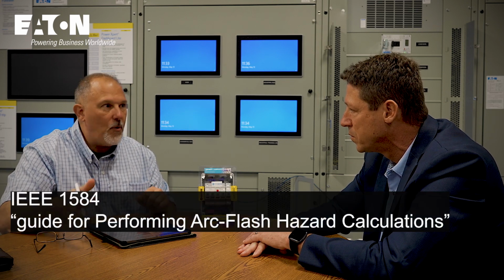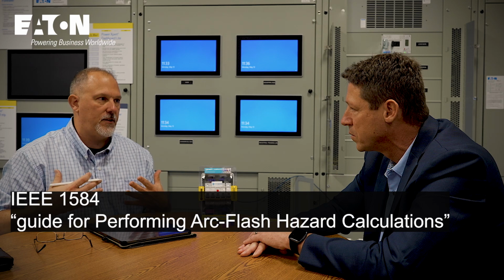We can calculate incident energy with calories per centimeter squared based on IEEE 1584, but we can't calculate the impact of shrapnel and all the things you just mentioned. We can't calculate the sound. And then there's the eye damage. You have a huge sound impact to your ears, eye damage, thermal burns, projectiles. We try to make changes to avoid all of that. That's our challenge.